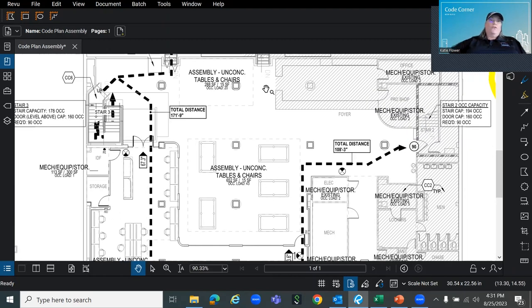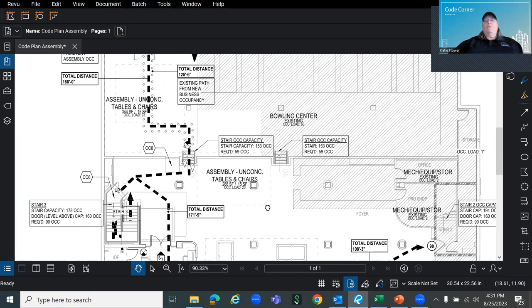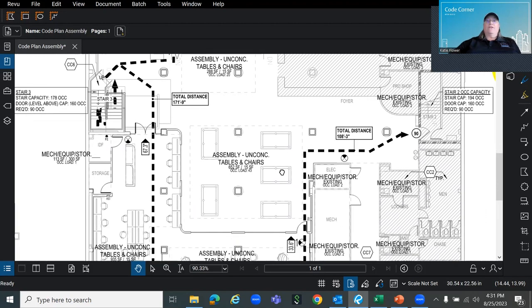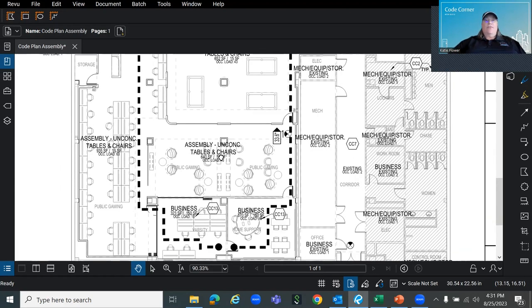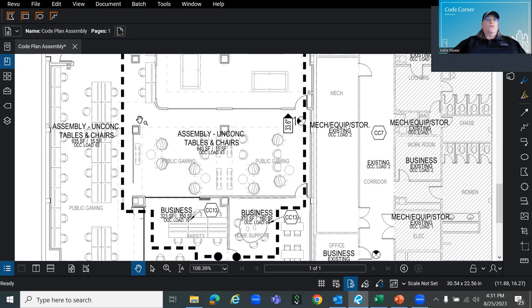And so the total for this floor means that if I have to lock or latch this stair door, I would need an exit device because it serves an assembly occupancy with more than 50 people. NFPA 101 says 100 or more people. And since IBC is 50, the more restrictive requirements take priority. They take precedence. You can tune into a past episode of Code Corner where I address that exact thing. So those are what you're looking for.